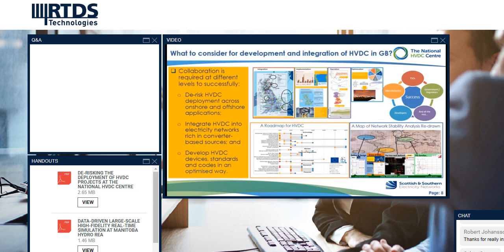So it's very important, whether it be multiple fault ride-through resilience, or the resilience of the PLL to track a given level of disturbance, or overvoltage or overcurrent protection that could occur at a given point in time - it's very important to integrate devices together with comparable levels of detail, and to understand, if not the detail of the layers of control within a model, at least the facets of that model so that you can describe an analysis solution within it. So that's the challenge that we're faced with.